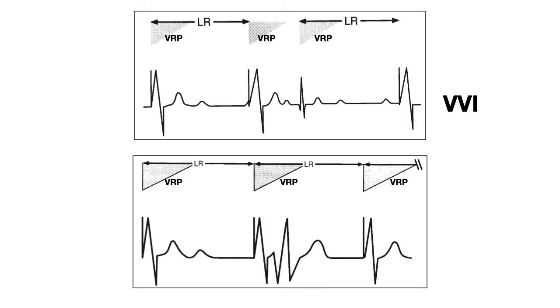The VVI pacemakers are refractory after either a paced or a sensed ventricular event, and this period is known as the ventricular refractory period, and here it is represented by the shaded triangle. Any activity that happens during this period will not be sensed and does not reset the timing circuit of the pacemaker. In the absence of a sensed ventricular event, the lower rate timer is complete and a pacing artifact will be delivered. However, if an intrinsic QRS complex, like a spontaneous or a premature ventricular contraction, is sensed, the timer of the lower rate limit will be reset and it will restart again from that point.